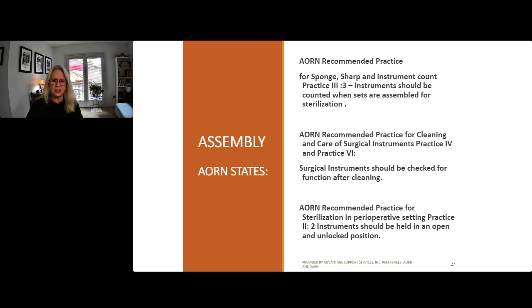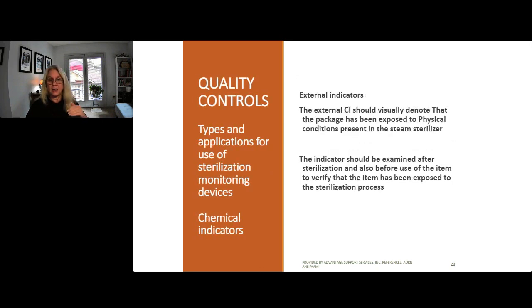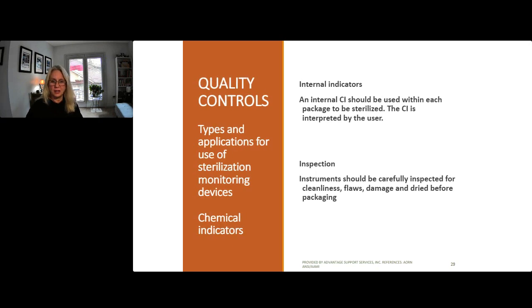One of the things that we do and we'll suggest is how do the sterile processing technicians in your facility understand how the instruments are used and the impact on those instruments if they are not working correctly. So there's some tools that we're going to talk to you a little bit about how to inspect for functionality. The CI quality control, the chemical indicator, should denote that the package has been exposed and it should be examined at the point of use. The internal integrator, another quality inspection check. These are all the recommendations from AORN or AAMI that support those steps that we said we were going to take before we close the tray.